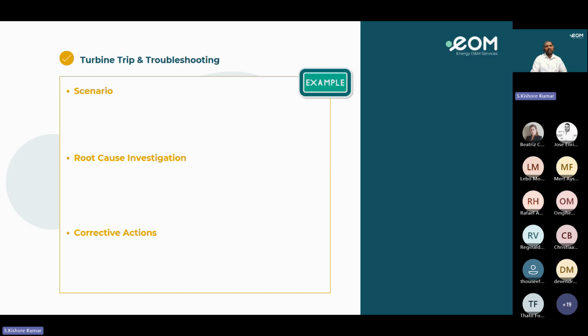An example of a turbine trip and a troubleshooting scenario. The event is a sudden turbine trip during load operation. The indicators are an overspeed alarm, a vibration spike, and main ESV activation.